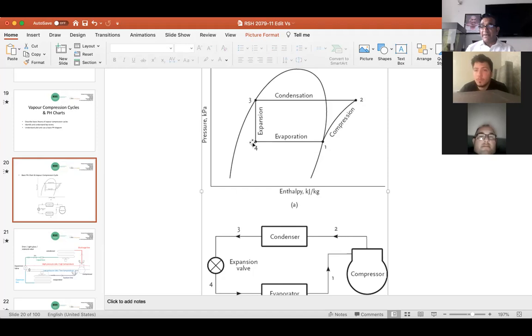So by having that subcooling here, the system performance is increased. We're getting better cooling, more cooling, more refrigeration effect, because we've elongated that line back here. We're making better use of the evaporator. So having subcooling means that we are increasing the cooling capacity, because that there is saturated liquid, and we're extending that line to be here, so it's getting closer to 100% saturated liquid.